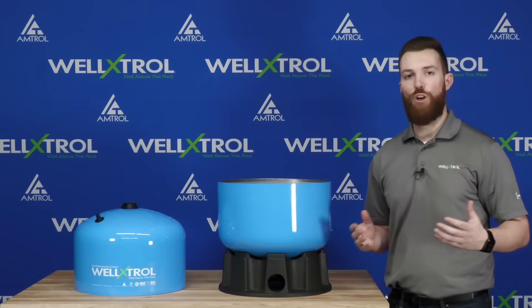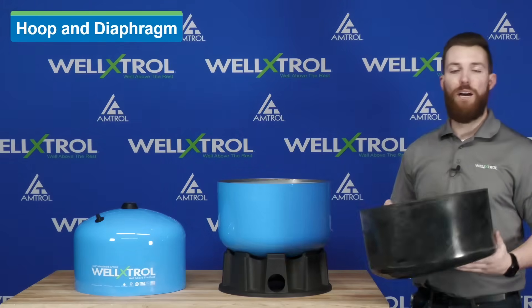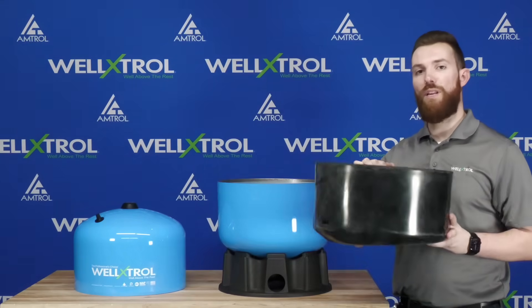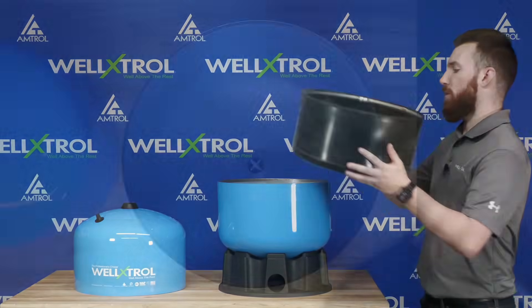The next step is our hoop and diaphragm, which is a very important component. This is what cycles within the tank and allows the air and water to be separated. The hoop and diaphragm is a full butyl blend — it's a thick butyl — and that's going to allow for longevity and durability of your Well-X-Trol. Let's go ahead and install the hoop and diaphragm.